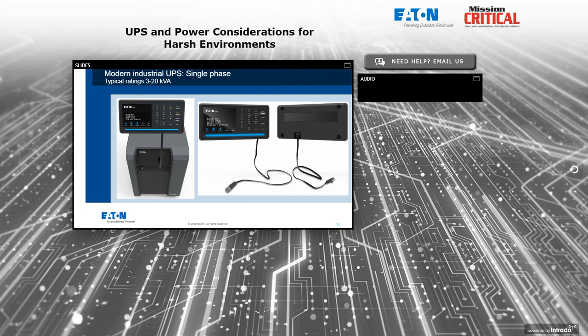It also automatically regulates its output voltage even as the input voltage changes, and does so without the need for complex controls that might be failure prone or subject to age degradation, etc. Ferro-resonant transformer has the ability to absorb surges and lightning strike style transients without the necessity for having traditional surge protection devices built in. So a ferro-resonant transformer, using primarily a special transformer and a capacitive tank circuit, provides voltage regulation, ride through with brief outages, surge protection, all without the need for complex controls that could suffer in harsh environments. That's why ferro-resonant UPSs are so attractive for this application.